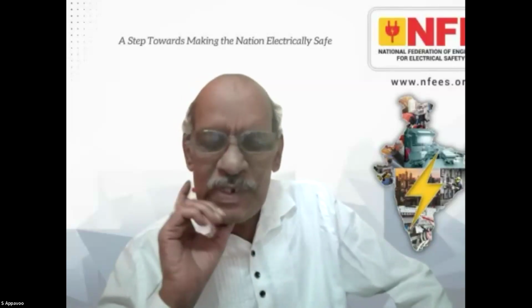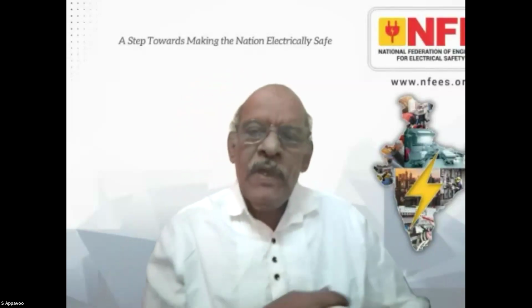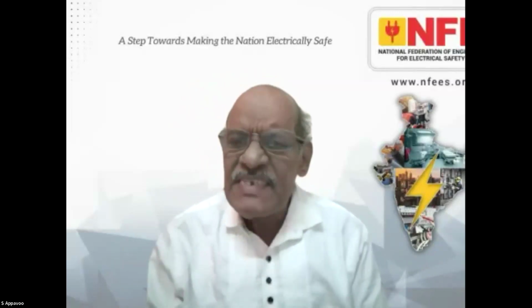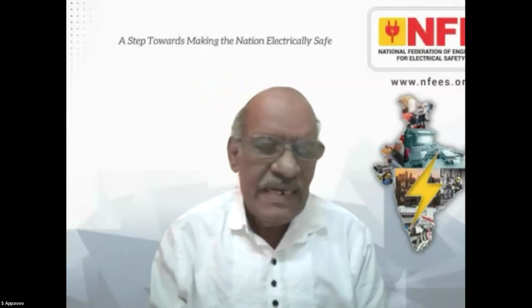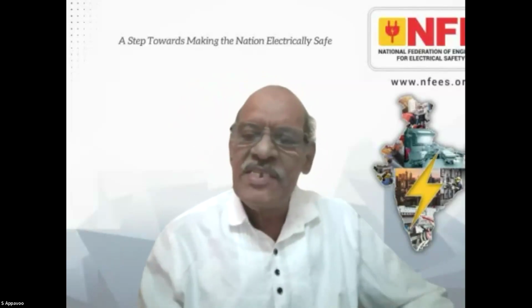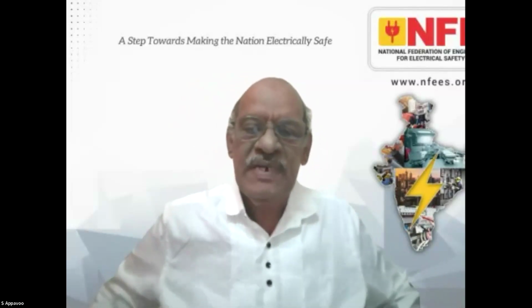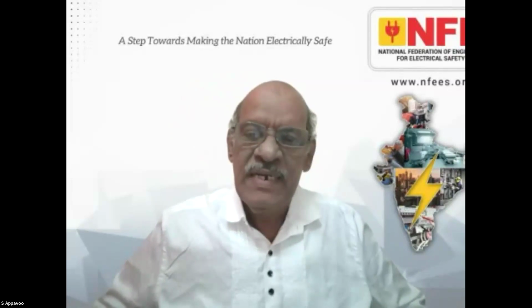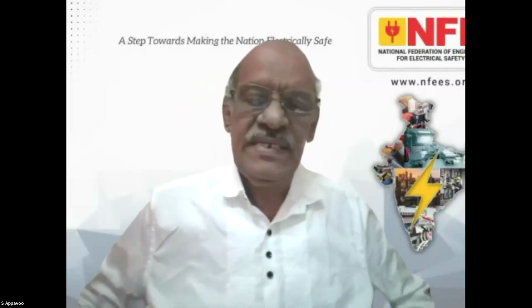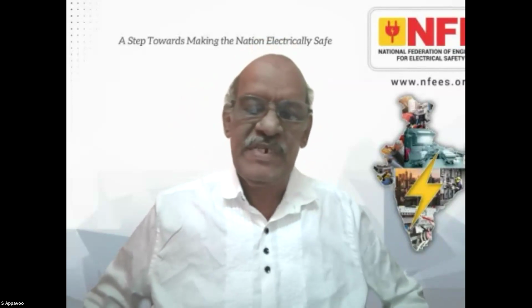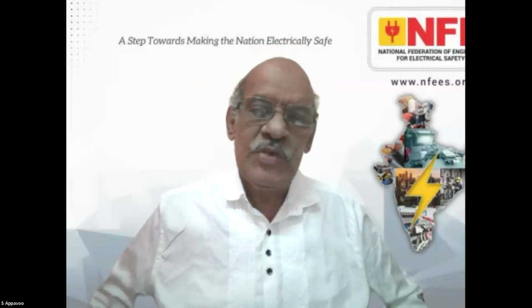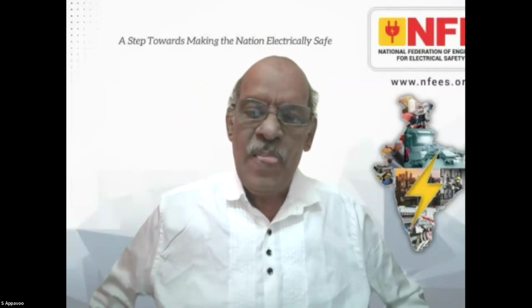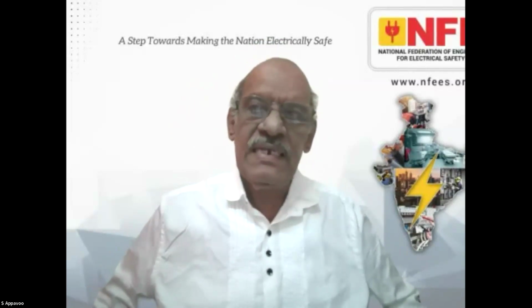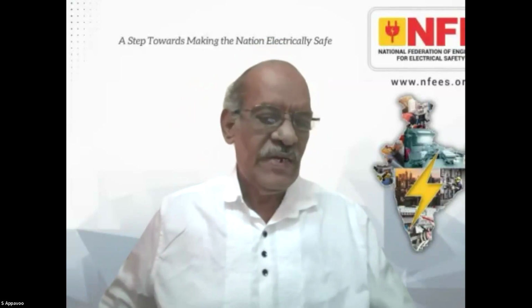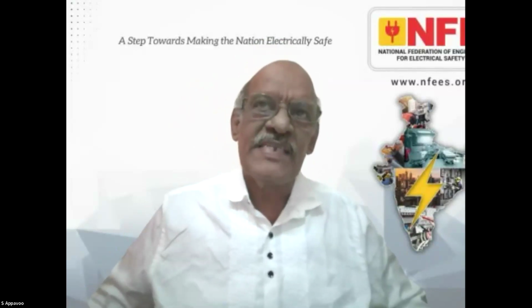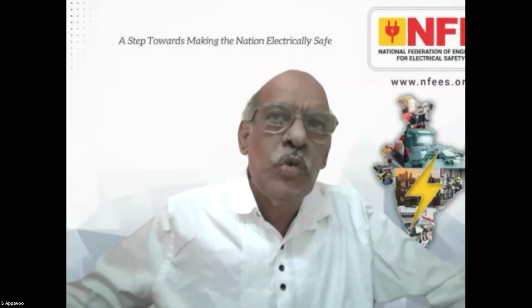So I would like to supplement your reply. Actually, the efficacy of earthing bonding requires a specific instrument, a four-terminal instrument, where voltage is injected and current is measured. So this four-terminal instrument is suggested for such measurement. There are figures in NEC also, you can refer. So ultimately what it says is it should not exceed 0.2 ohm.